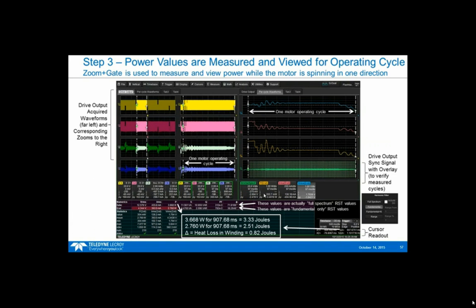Now if we use our Zoom+Gate capability, this is our drive output waveforms, the full 5-second acquisition. Then we're going to zoom into one operation of the motor after reversal, operating in one cycle in one direction. We've turned on our drive out sync signal, and you can see these alternate color-coded overlays. From previous webinars, you may remember that represents one of these calculated periods. So we can use that to verify that we're capturing all the periods of this motor operating cycle.